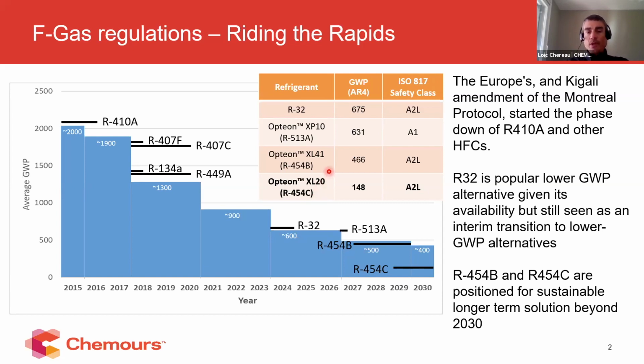Why now these two products are being positioned, it's mostly also because of the performance they can bring into the heat pump. And let's say if the 410A refrigerant is being used as a reference, the near drop-in solution that can really be considered as a good candidate to achieve the higher efficiency from the 410A refrigerant is the 454B. And this is really the near drop-in refrigerant that can be seen coming from the 410A.